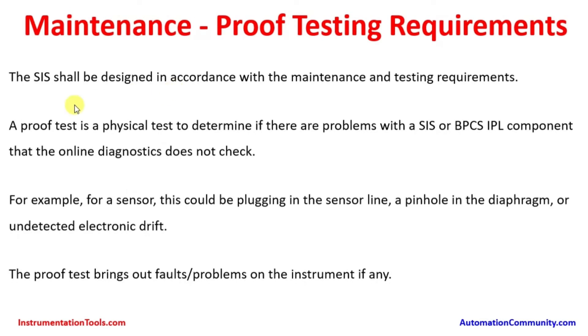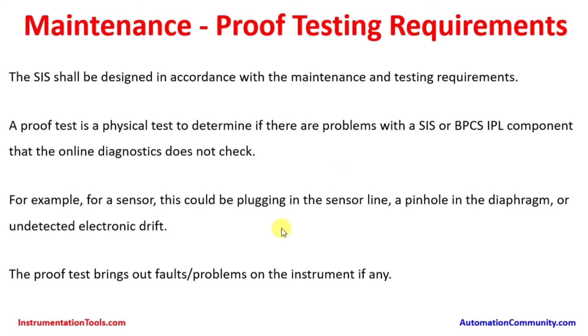Proof testing requirements. The SIS shall be designed in accordance with the maintenance and testing requirements. A proof test is a physical test to determine if there are problems with the SIS or IPL — independent protection layer — components that online diagnostics does not check. For example, for a sensor this could be plugging in the sensor line, a pinhole in the diaphragm, or undetected electronic drift. These are all hidden failures, and during proof testing these failures could be revealed. That is why it is always recommended to conduct proof testing as per the calculated cycle. The proof test brings out latent problems on the instrument if any, and those problems will be highlighted upfront.